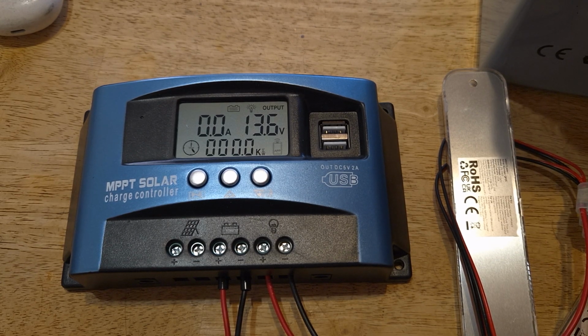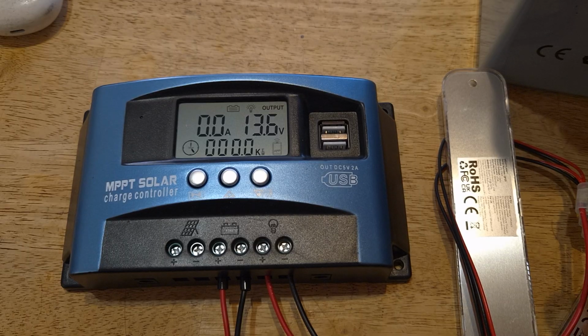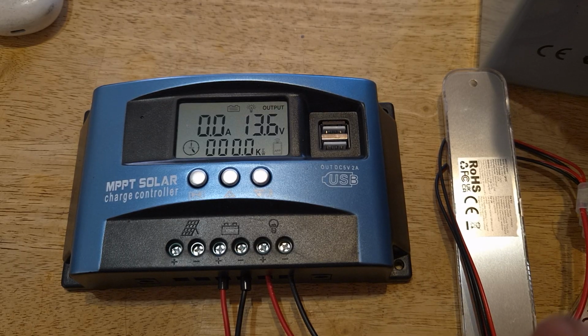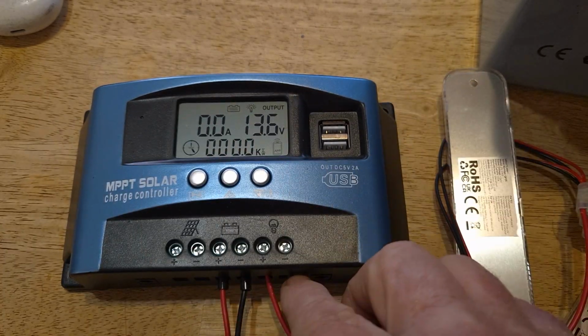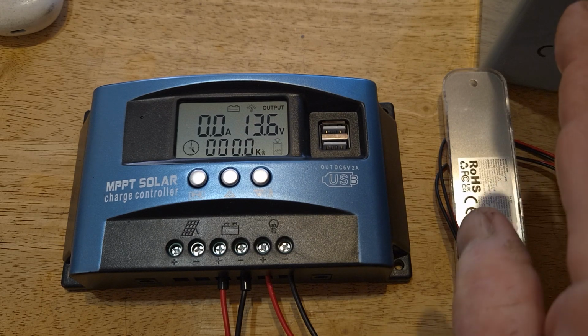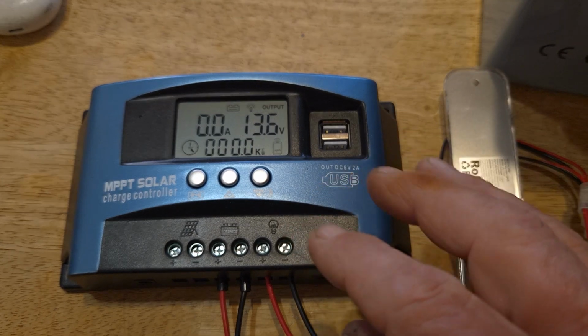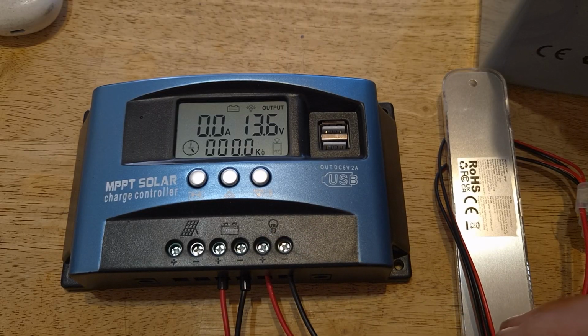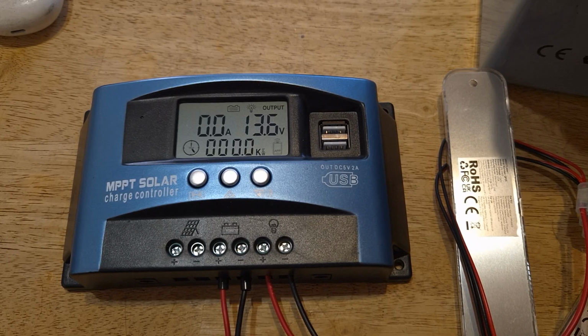You can always ChatGPT or Perplexity about what these mean, but then write down the value. And then it says modify the discharge recovery voltage. The discharge recovery voltage is once you've gone below, say, the battery BMS - which we'll get to on the next setting - once it has cut off the power to the load because the battery is too flat, what voltage do you want to set it at so that this thing can safely provide a load again? Because you don't want to start it at 11 volts and now you're starting to pull current, or your solar's kicking in, the sun has come up, and you don't want it at 11 volts, or 13, or 10.7 or 10.8, to start putting a load out.